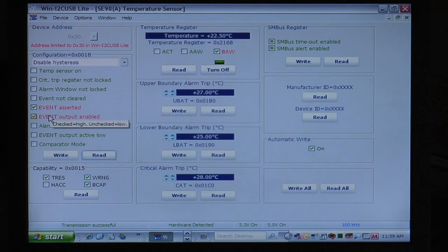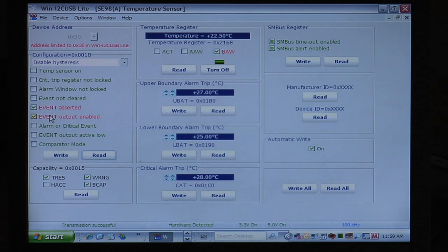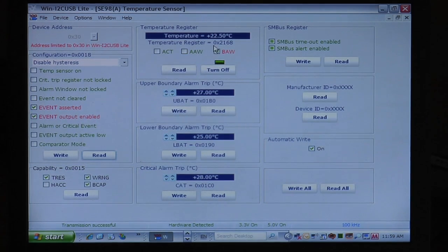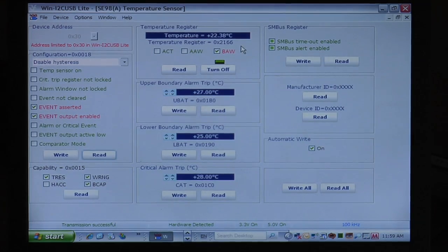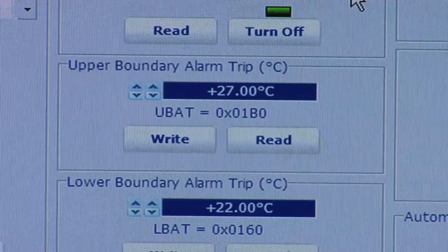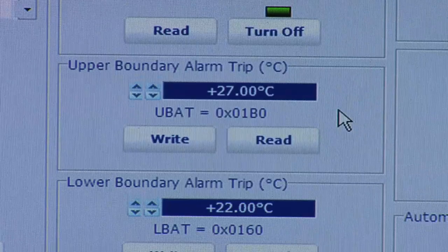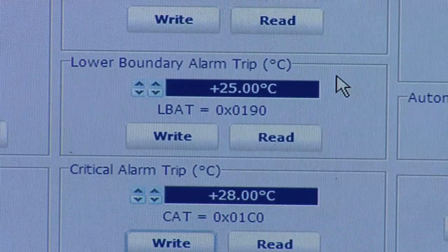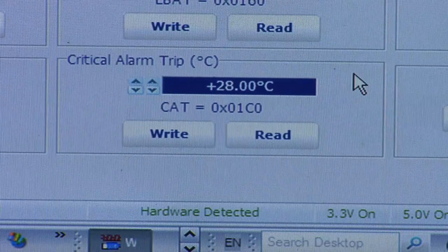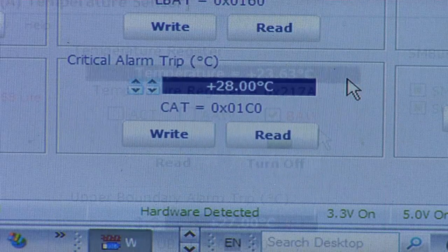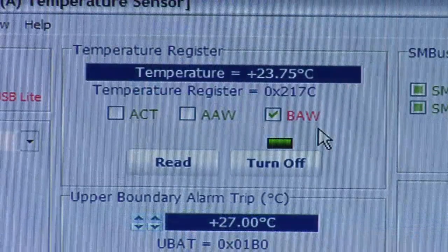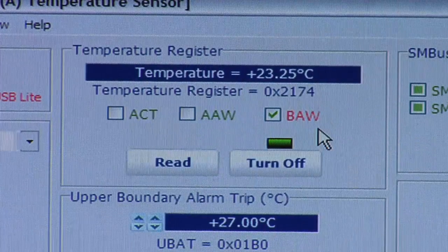Next, in the center panel, we see both the current temperature reading and three different alarm registers. These are the upper boundary alarm trip value, the lower boundary trip value, and the critical alarm trip value. These are programmed for 27, 25, and 28 degrees respectively. Note the room temperature is about 23 degrees today.